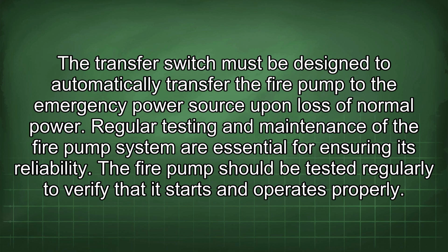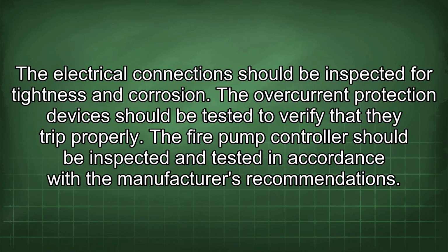Regular testing and maintenance of the fire pump system are essential for ensuring its reliability. The fire pump should be tested regularly to verify that it starts and operates properly. The electrical connection should be inspected for tightness and corrosion. The overcurrent protection devices should be tested to verify that they trip properly. The fire pump controller should be inspected and tested in accordance with the manufacturer's recommendations.